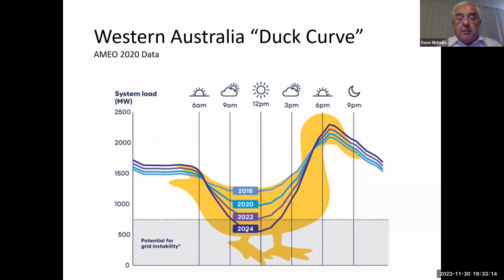And there's three problems that brings you. The first problem it brings you, or two problems. It brings you a stability problem because you've then not got enough running machinery that is synchronous generation. You're running inverter-based machines. You need to add more things like synchronous condensers to your system, which adds money, but no one mentions that. So that's the first one.